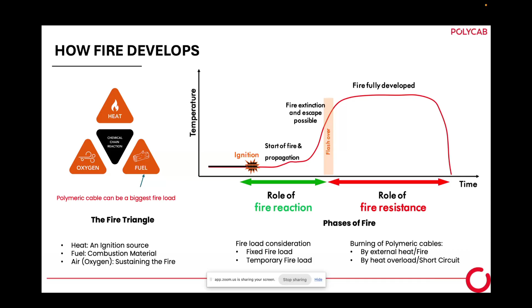So this is another time temperature curve. In UK, some people tested by burning material in a tunnel to see how much temperature develops in a full fire situation. This was taken as a graph, and ASTM, American Society for Testing Material, also worked on this, and they formed a curve showing that when fire takes place, temperature rapidly goes up to 700-750 degrees. After that it rises slowly to a maximum of 1100 degrees. This 1100 degree temperature forms at the top of the tunnel.